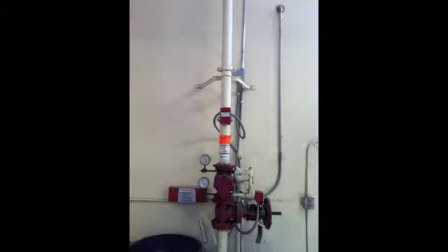Here we have a numerous amount of things. We have the riser, which is the pipe that supplies all the sprinkler heads with water at all times, because this is what you call a wet pipe system. The pipes in this system are filled with water at all times. When a head is activated, water immediately flows from it. Water is supplied to this system by a gravity tank, pressure tank, automatic fire pump, and water service system.